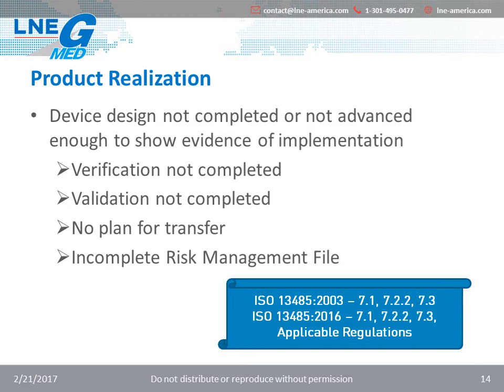Next common pitfalls are related to product realization, starting with design when applicable. The product design shall be completed or very close to it, to allow an auditor to state on the conformity of the whole section 7.3 of ISO 13485. Non-conformities are issued when verification and/or validations are not completed yet, if there is no plan for transfer, and we will see that in the next slide on manufacturing, or when the risk management file is incomplete. In addition to the ISO 13485 requirements, most of the regulations also request for the device design, when applicable, to be completed to obtain product approval. It is the case for the European Medical Device Directives as well as the Canadian Medical Device Regulation.